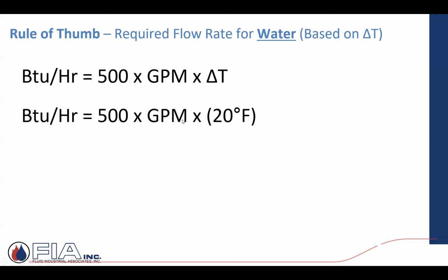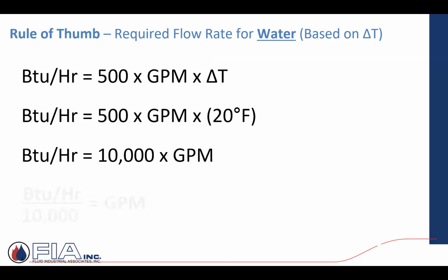And so if you start plugging in these numbers and we stay with that example that we had, the 20-degree drop between the inlet temperature to the coil and the outlet temperature, we can say BTUs per hour equals 10,000 times the flow rate. And in this case, we're trying to establish the flow rate. So we just reorient the equation and say BTUs per hour divided by 10,000 will get me my GPM, my flow rate, my gallons per minute.